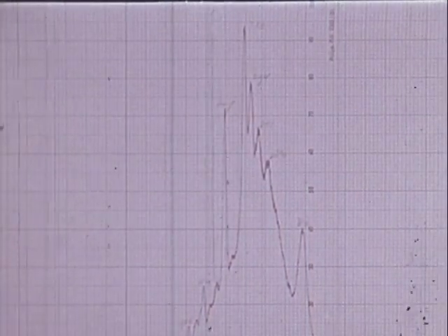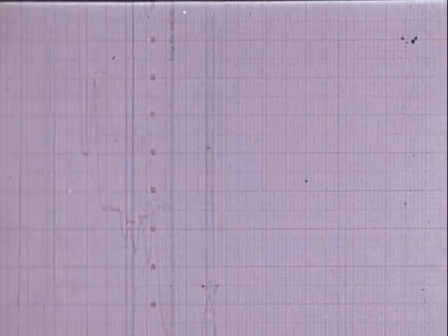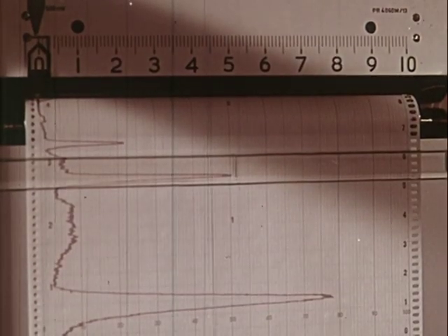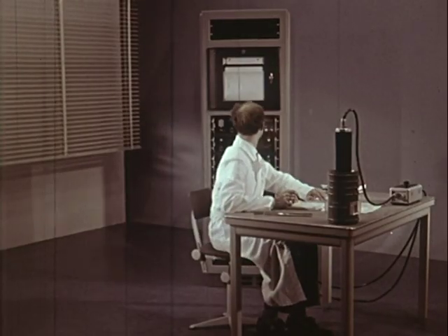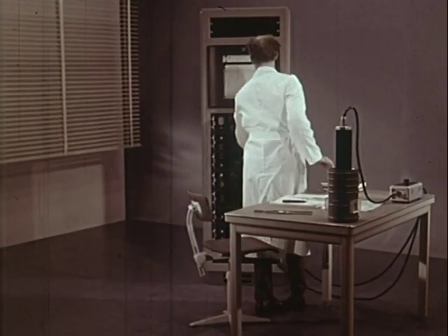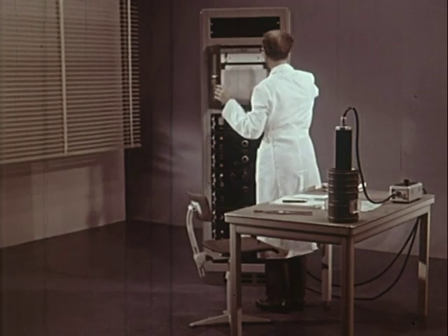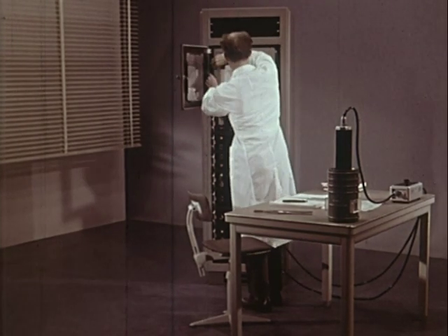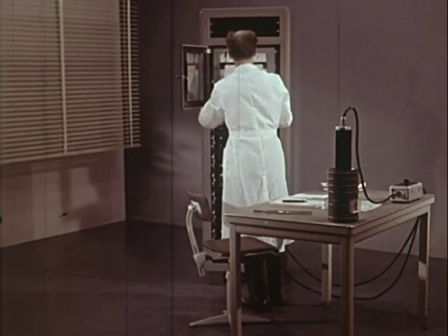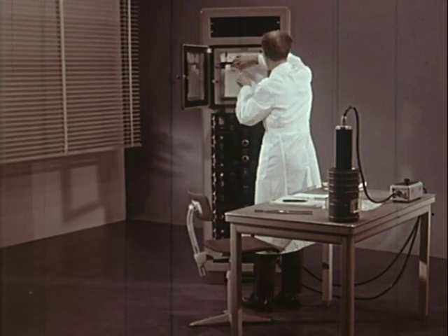A spectrum of radium-226 obtained by gain scanning. The spectrum of the same isotope scanned with a sliding channel. Philips spectrometers provide means to scan gamma energy spectra either with the sliding channel or with the gain scanning method of operation, manually or automatically. Either method may be chosen to conform to the requirements for each particular sample.